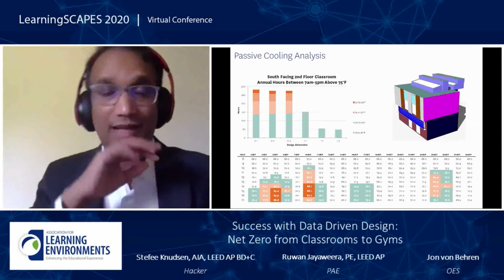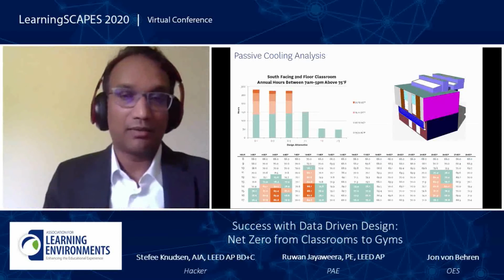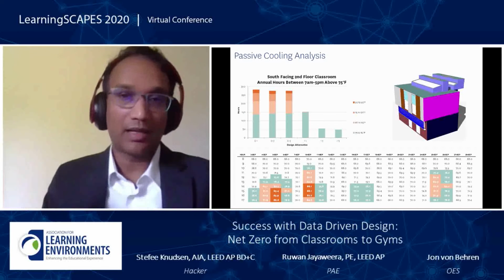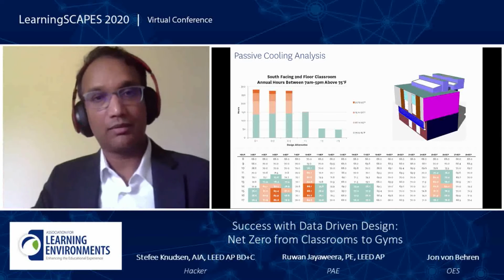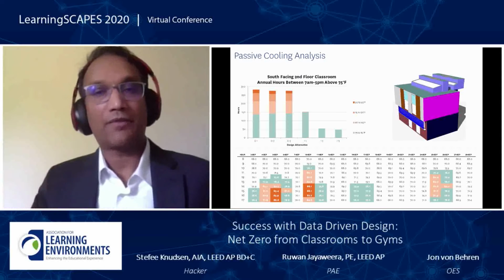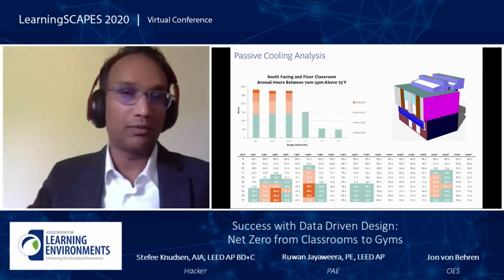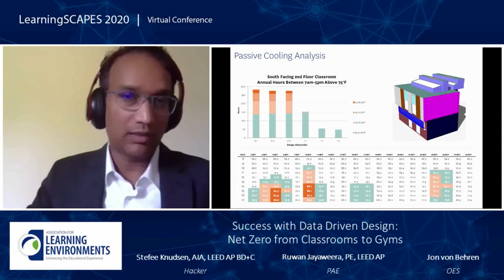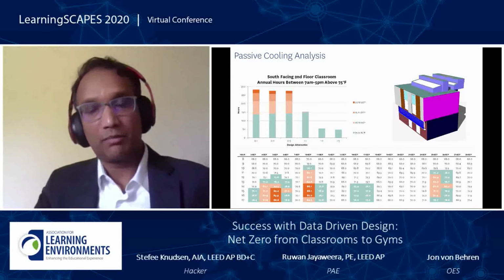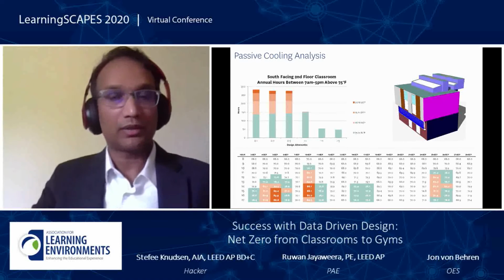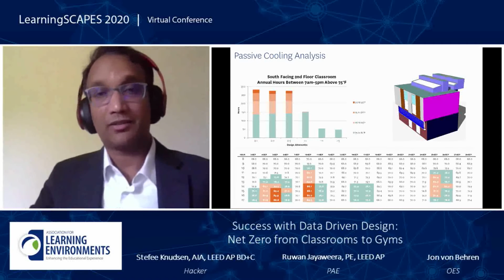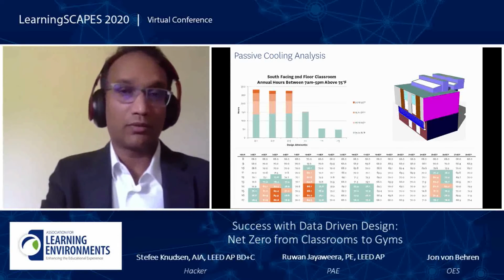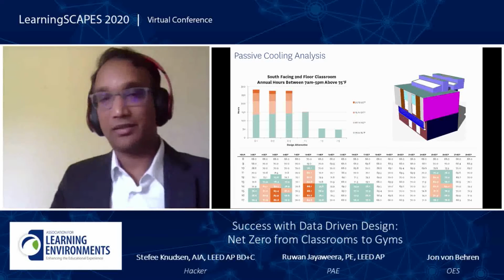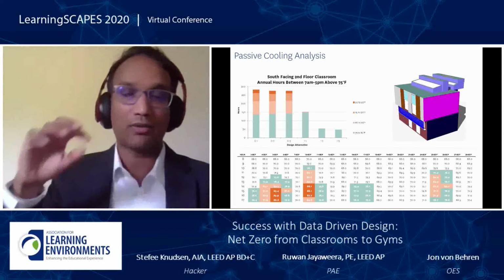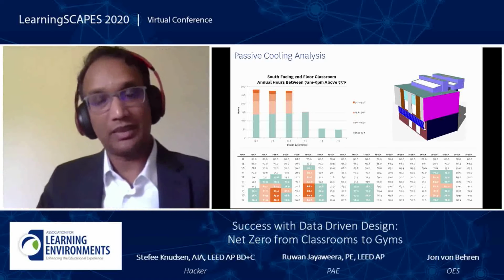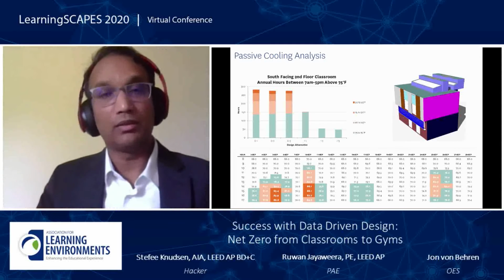Now, passive cooling is not as easy because it is time-based. There's a lot of factors going into heating and cooling load. So we actually have to build a computerized model and do an annual simulation of it. So this is kind of a snapshot of what our model looked like. We did the worst case classroom, like Steffi mentioned, in the lower school. We just did the southwest facing upper classroom because that was the worst case in terms of heating and cooling load.